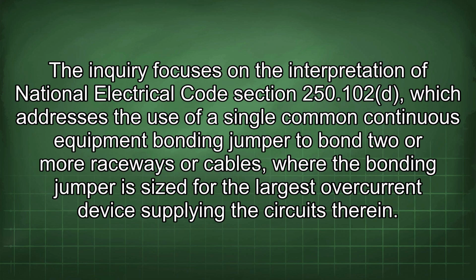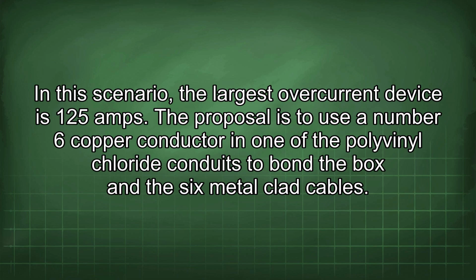250.102, which addresses the use of a single common continuous equipment bonding jumper to bond two or more raceways or cables, where the bonding jumper is sized for the largest overcurrent device supplying the circuits therein. In this scenario, the largest overcurrent device is 125 amps.